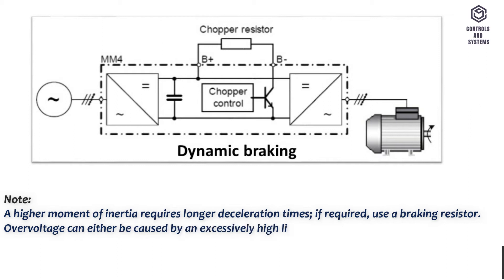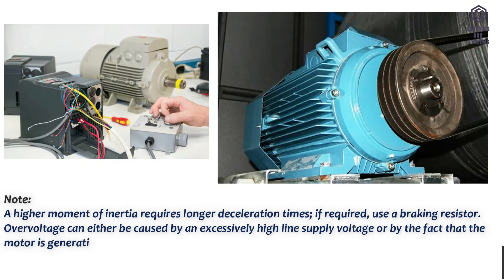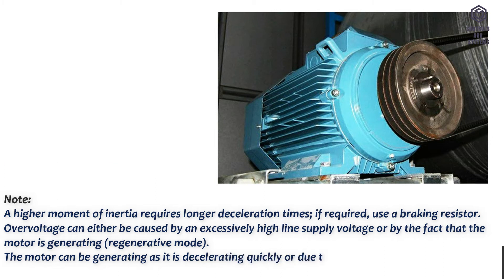Overvoltage can either be caused by an excessively high line supply voltage or by the fact that the motor is generating, regenerative mode. The motor can be generating as it is decelerating quickly or due to the fact that an active load is driving the motor.